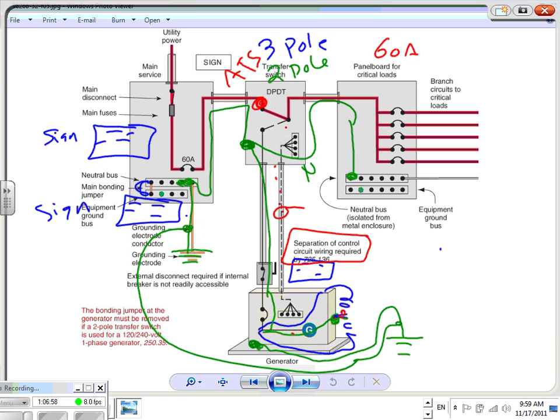Now what happens when the power comes back? When the power comes back, it senses that there is power, and it waits for 50 minutes. We have a delay on them. It waits 50 minutes to make sure that it's coming back for good, because sometimes it comes back and goes off again. Once the power is stable after 50 minutes, it switches you back to the utility, and it waits for what they call idling. It waits for 5 more minutes. After 5 more minutes, the generator will run 5 more minutes to idle, to cool down, and then it turns the generator off. All this is happening through the control system between the auto transfer switch and the generator.